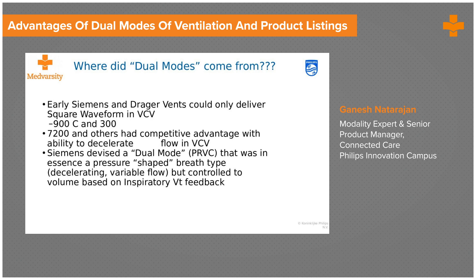To compete against this — because as soon as you have a decelerating flow waveform, as we have seen in a graphic earlier, there is a mild drop in pressure — the first company to come with a dual mode was Siemens, now Maquet, called PRVC: pressure regulated volume control, where they started delivering volume in a pressure-type waveform. That is the origin of the dual mode, specifically PRVC.